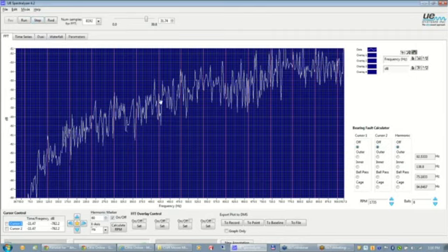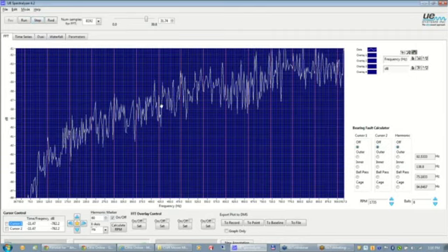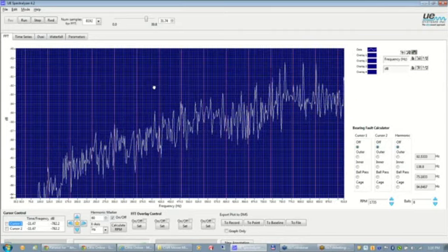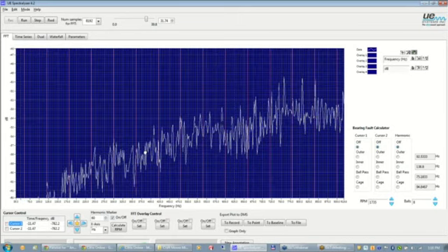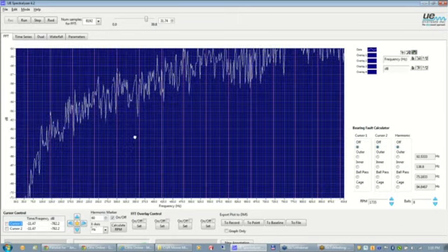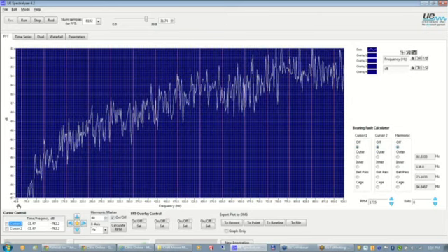So what does that tell us? Well, if we look across the spectrum here, I'll pull this down so we can see. Here's our first 60 Hertz harmonic on the left-hand side, and we can determine that as well looking on the bottom axis here in between 48 and 75, and then your subsequent harmonic frequencies here of 120, 180, 240, 300, and so on up the line.